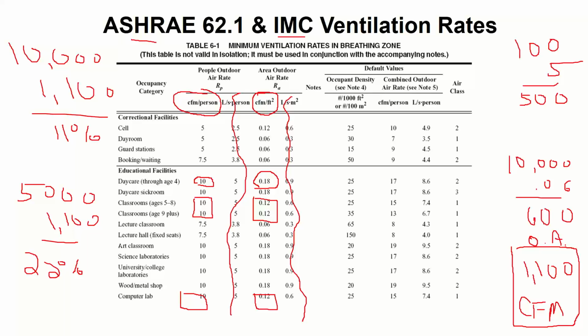The VOCs won't be taken care of at night, because there's no one there, so who cares if there's VOCs in the space? But I usually program it, as many people do, so that if my building goes occupied at 7 a.m., I'll start my ventilation cycle at 6 a.m., giving an hour of runtime to purge all the VOCs out of the space, since they accumulate over the day.